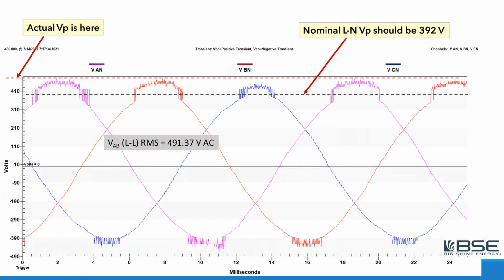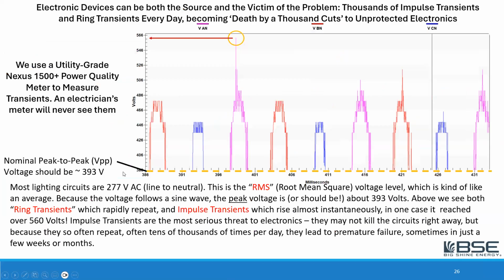But if I look at the waveform with a high-speed meter that's recording hundreds of samples per electrical cycle, then I see something that looks ugly. As you can see at the crest, there are all these different repeating transients, and the actual peak voltage is much higher than the nominal peak voltage should be. So that's what you want to focus on. Your electronics were designed for this black dotted line at 393 volts. That's for a nominal 277 volt circuit, where the peak would be 392. But we're getting way up here, well up into the 400s, and then there'll be impulses that'll be up over 500. Here's an example where you can see those impulse transients.